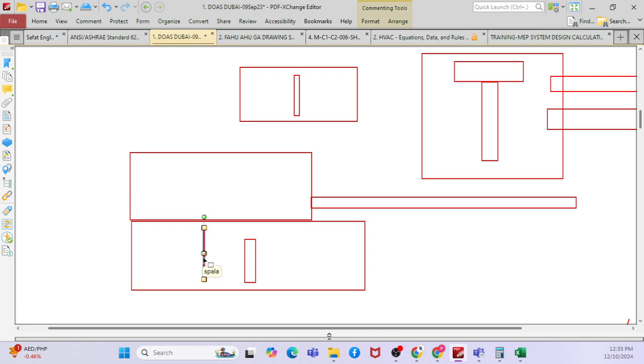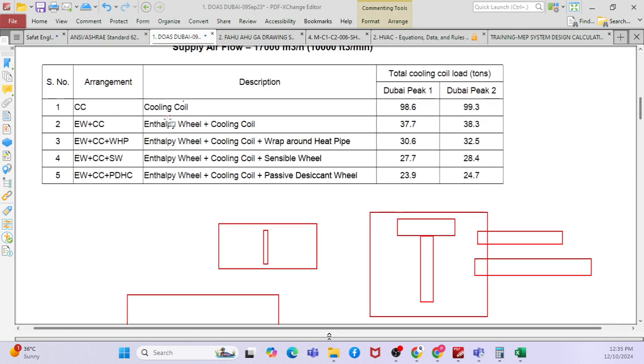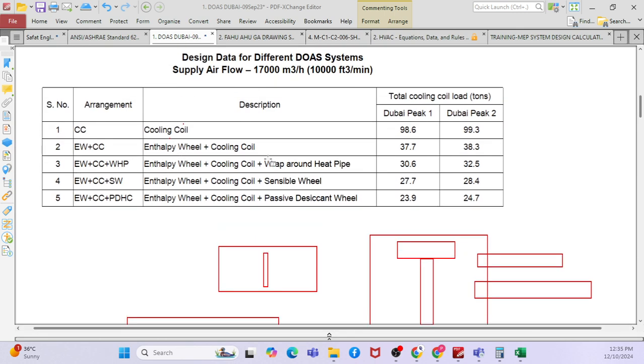As for the capacity calculation, how to calculate the FAHU airflow rate, how to calculate the capacity and what the method is, we have seen everything. But based on the energy consumption, you will select which type is better. It's clear? In the actual situation you will see the comparison. Whenever you are doing a project, you will ask the manufacturer to give different options. One with the heat pipe, another with the double heat wheel. Then you will see which is the best one, right?